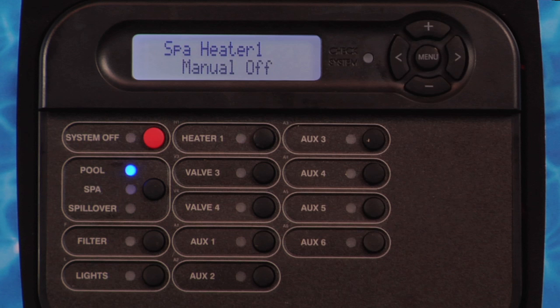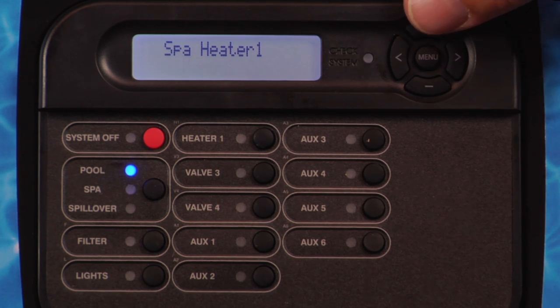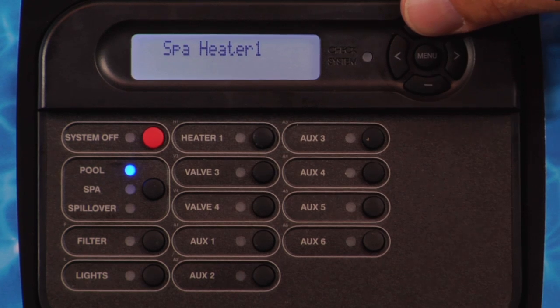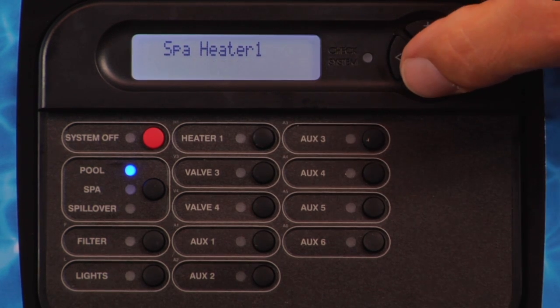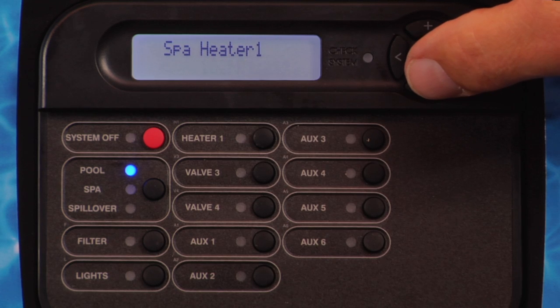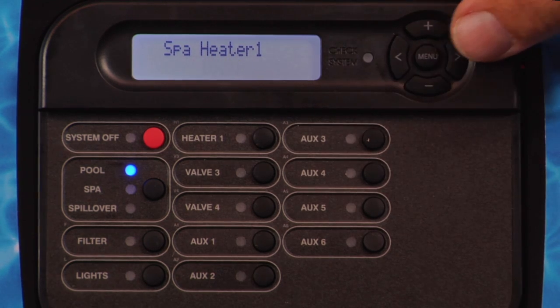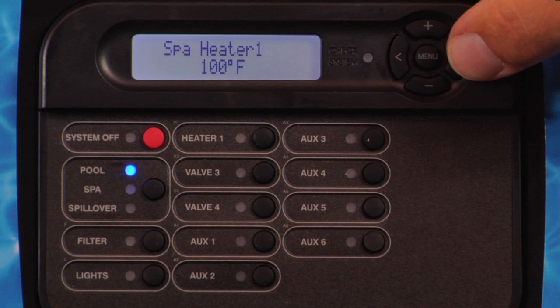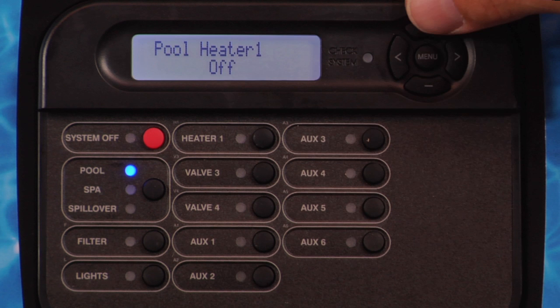All other settings are dependent on various pieces of equipment being enabled. If Heater 1 is enabled and the ProLogic is configured for Spa only or Pool and Spa, Spa Heater 1 will be displayed. Pressing the plus button will adjust the temperature from off to 65 degrees Fahrenheit through 104 degrees Fahrenheit and then wrap around. Pressing the minus button will adjust the temperature from off to 104 degrees Fahrenheit through 65 degrees Fahrenheit and then wrap around. Press the right arrow button.